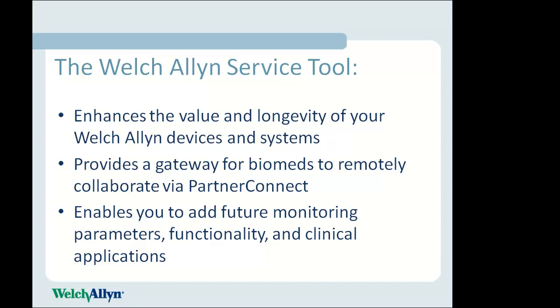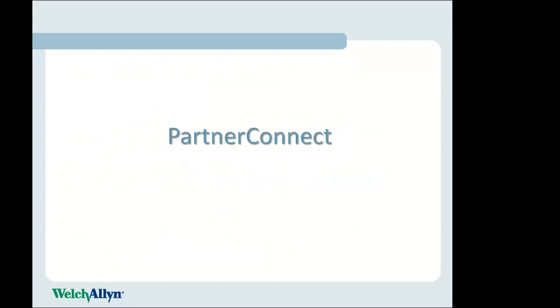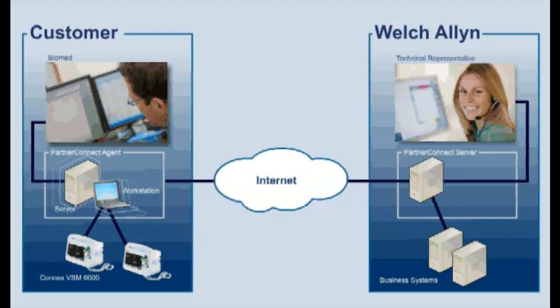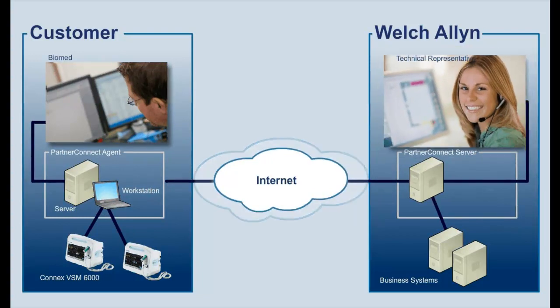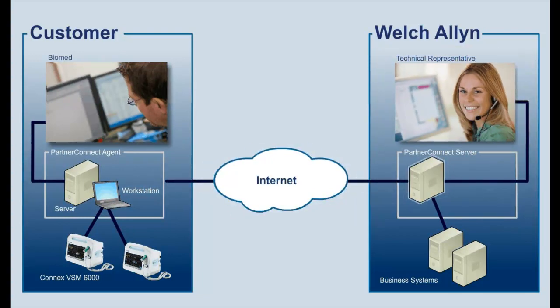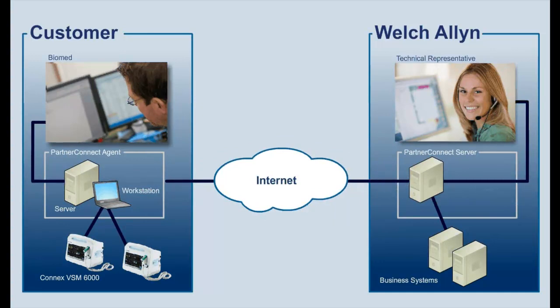Let's gain a better understanding of Partner Connect before we delve deeper into learning about the Welch Allyn Service Tool. Partner Connect allows a Welch Allyn Technical Support Representative to assist customers with solving device or system problems by directing them on what steps to take next, or, with customer permission, take control of the customer's PC while running the Welch Allyn Service Tool. By connecting remotely to the device in question, the representative can retrieve device maintenance logs for fault analysis, run remote diagnostics, and run performance tests to determine the cause of the problem and recommend the best solution.